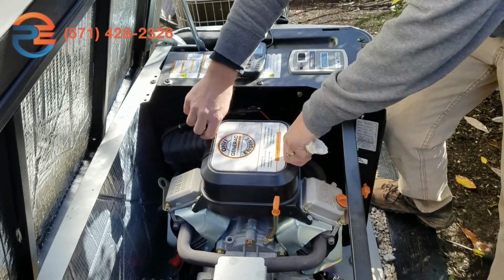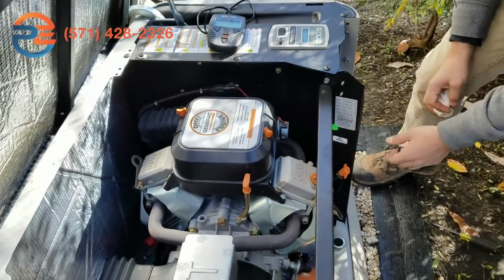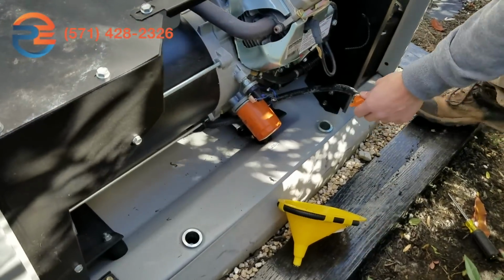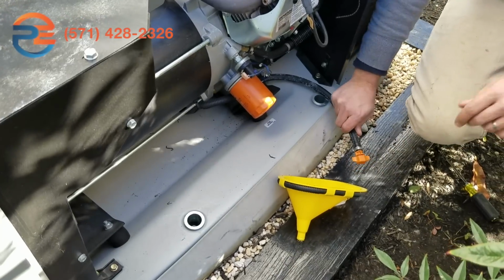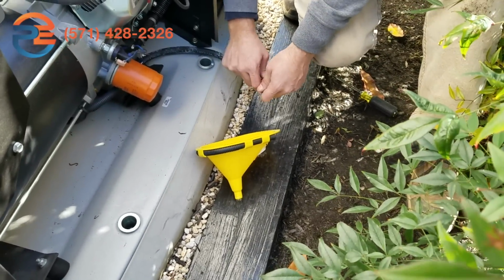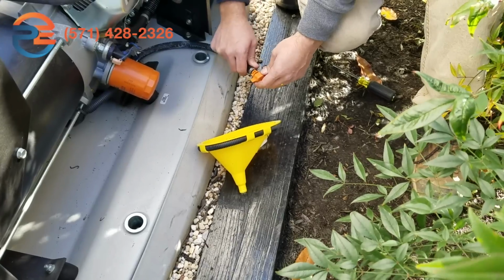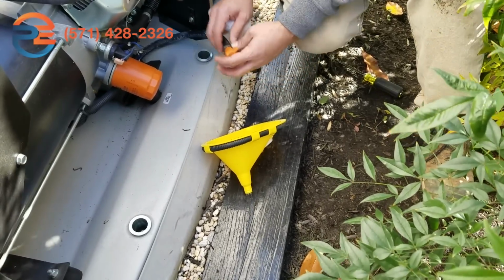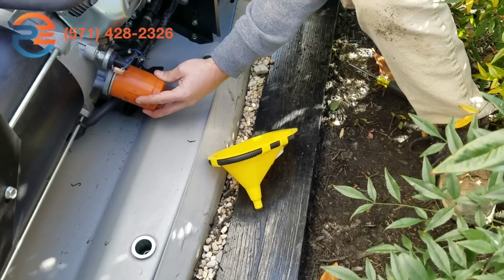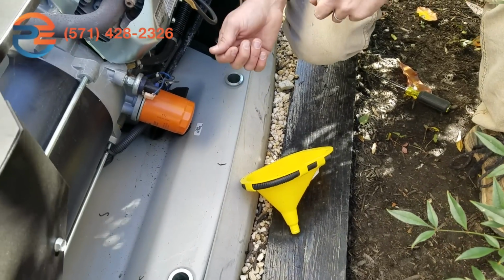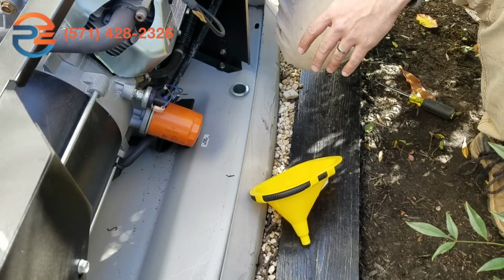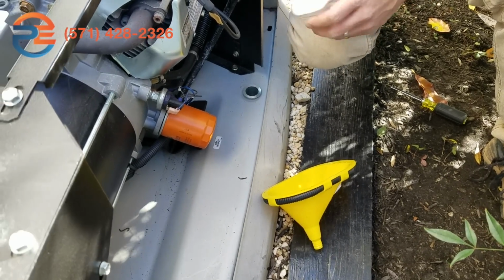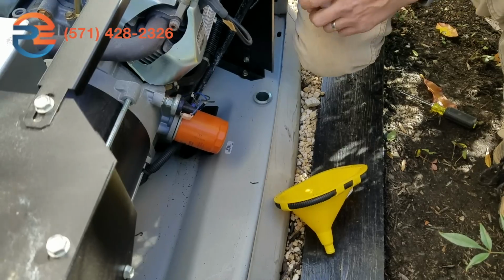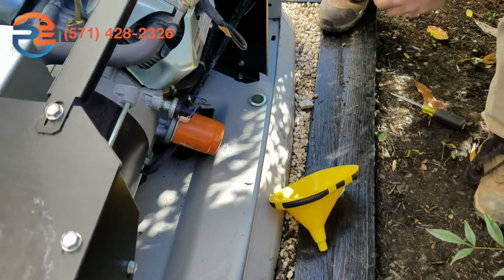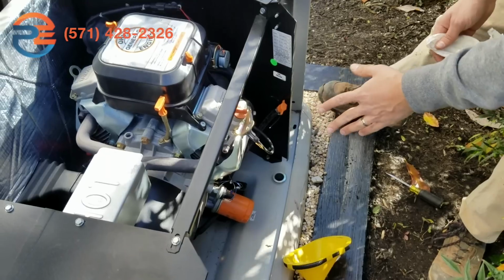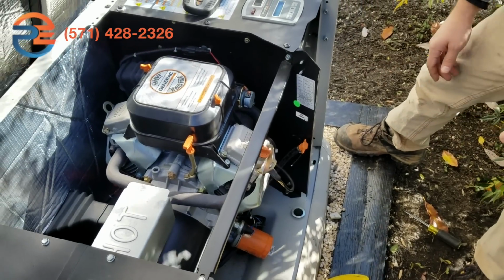Should you have to change the oil in your generator, you're going to want to access your oil drain hose and valve. Bring this down below the oil level, loosen the wing nut, and drain it into an approved container. Once all of the oil is drained, you're going to want to remove the oil filter, install a new oil filter, and refill with oil. This particular model takes roughly 1.8 quarts of oil, so just under 2 quarts. This is also a lot better to do if the oil is warm, so I always recommend running the generator before doing this.